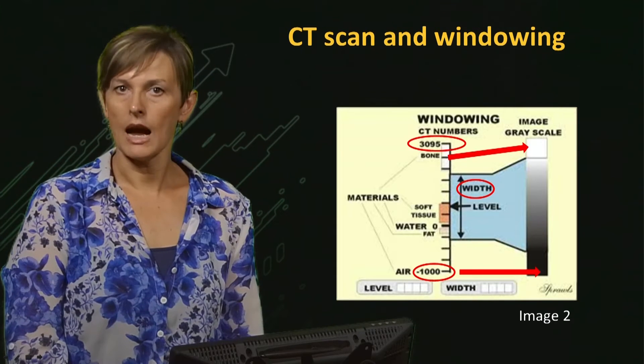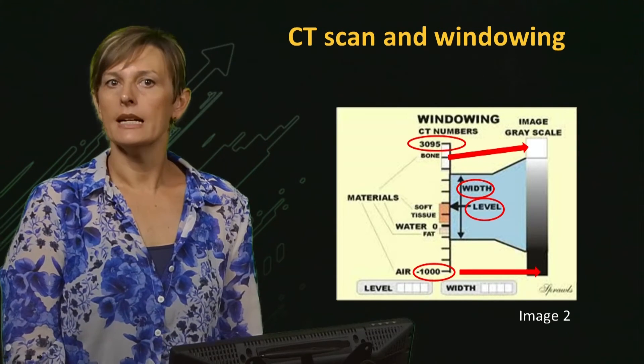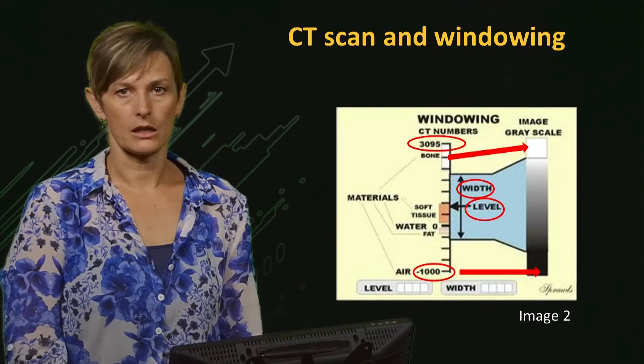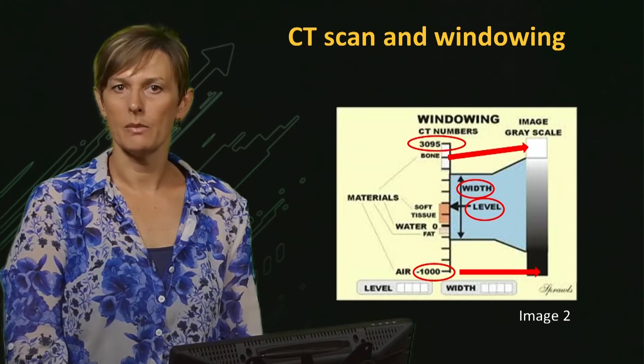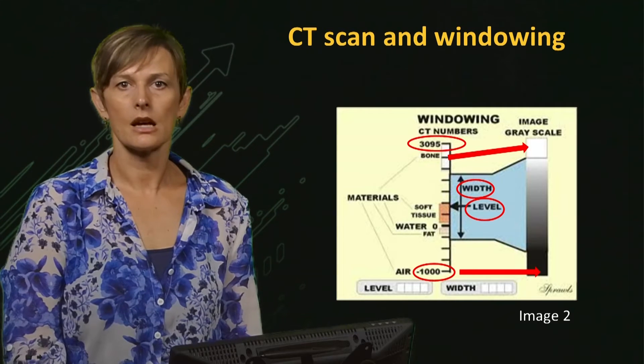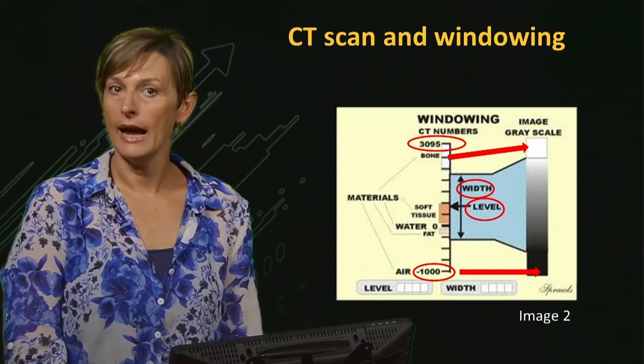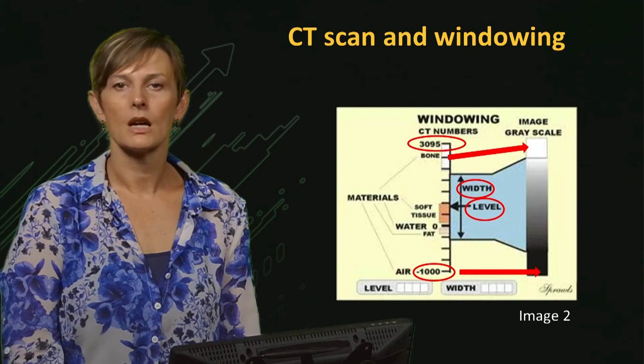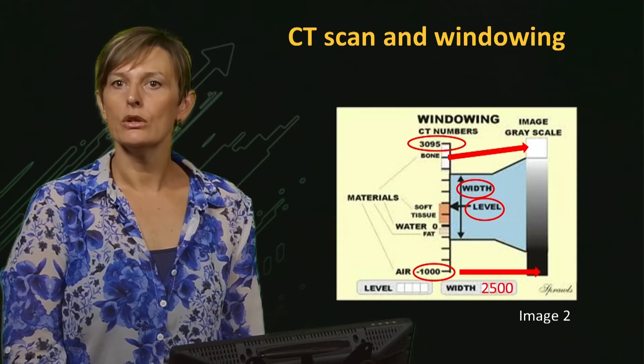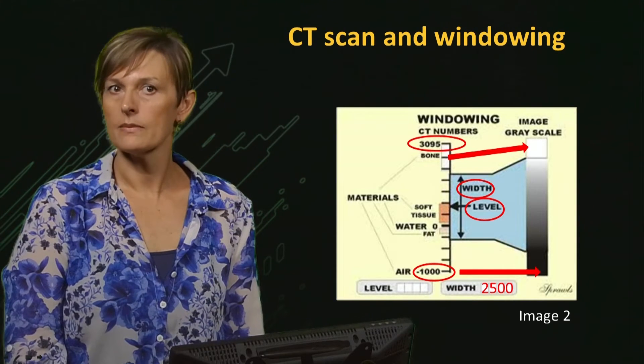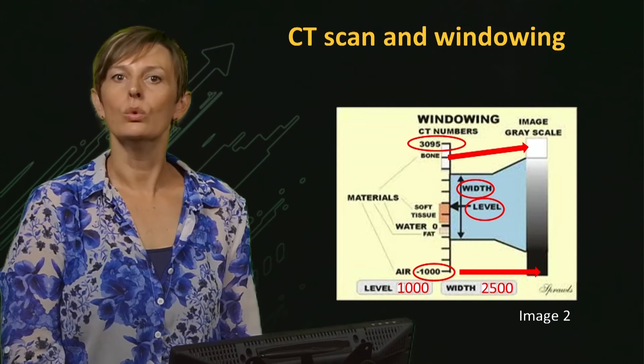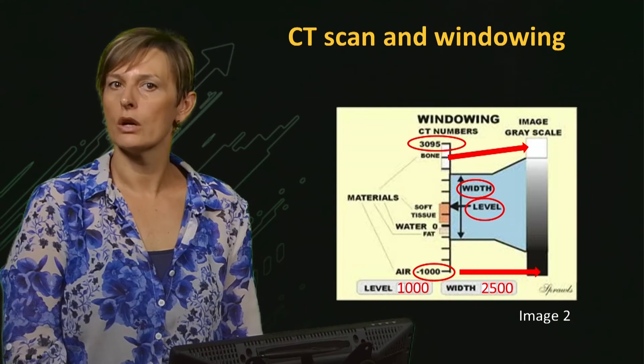The second factor, L, is the window level. It controls and adjusts the center of the window width. This factor can be used to optimize the image contrast within an organ. In practice, a variety of different values of L and W are used. For example, during bone imaging, W would be set to 2500 and L to 1000 HU. And the window would be shifted up towards the white scale.